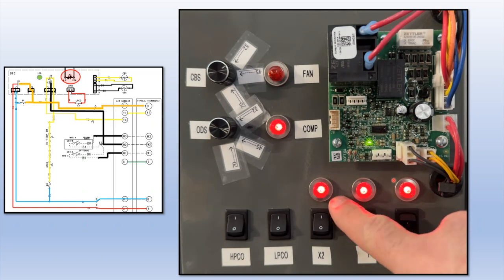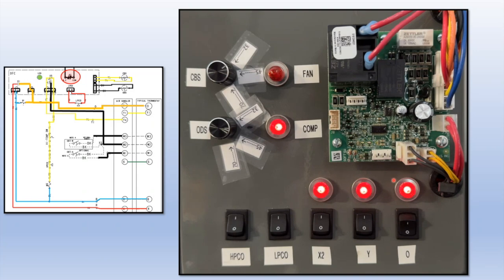And you'll also see that the X2 was illuminated, because X2 is going to go to your W on your indoor unit, so that during a defrost, either your furnace heat is going to come on or your electric heat in your air handler is going to come on so that cold air doesn't come out of your vents.